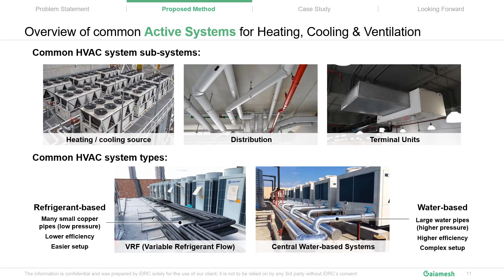The common HVAC system types are generally two large types: VRF, or variable refrigerant flow systems, and central water-based systems. One uses refrigerant and one uses water. As an architect, you can tell the difference by looking at the pipes. Refrigerant-based systems have many smaller copper pipes since they're not at high pressure, whereas water-based systems have large, consolidated pipes. That's one quick way of telling which is which.